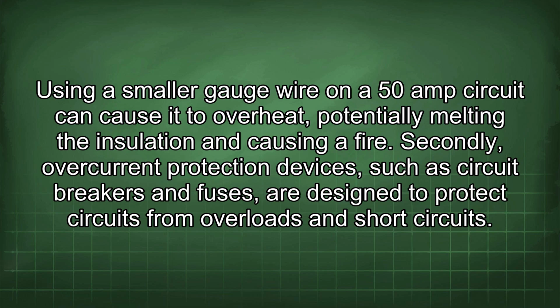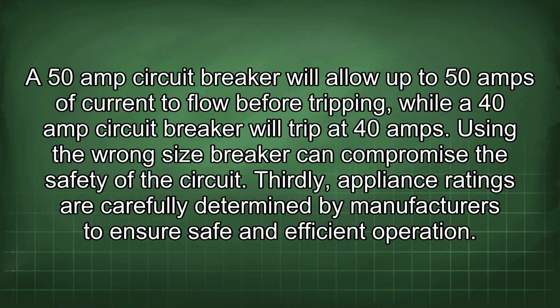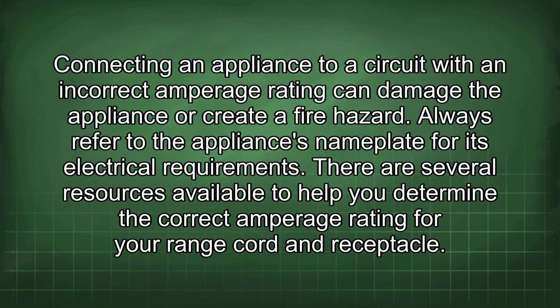and short circuits. A 50 amp circuit breaker will allow up to 50 amps of current to flow before tripping, while a 40 amp circuit breaker will trip at 40 amps. Using the wrong size breaker can compromise the safety of the circuit. Thirdly, appliance ratings are carefully determined by manufacturers to ensure safe and efficient operation. Connecting an appliance to a circuit with an incorrect amperage rating can damage the appliance or create a fire hazard. Always refer to the appliance's nameplate for its electrical requirements.